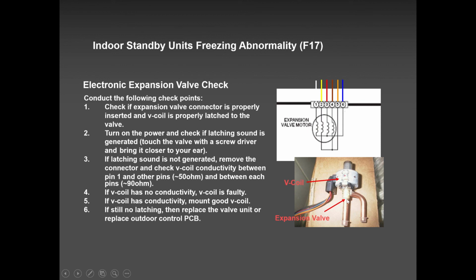Okay, so when the unit starts in cooling, it goes into vacuum, and you're positive that both lines are open, your Allen keys are fully seated out. Okay, they're fully out. That means that this electronic expansion valve coil or the valve body is clogged, or the coil is closing this valve and causing the unit to go into pump down. So the first thing you would do, the easier thing, is to change this coil.